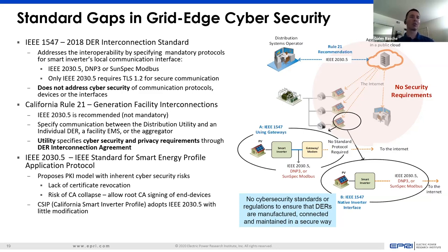In California, we have California Rule 21, which looks at generation facility interconnections. If you look at the graphic on the right, at the very top you can see the Rule 21 recommendation for interconnection between the distribution system operator and, in this case, the aggregator system in the cloud. It's just one potential interconnect, and it recommends 2030.5. But as shown by the large red circle, that doesn't drive any requirements for how an aggregator might interface with the smart inverters themselves, or any security controls on that.